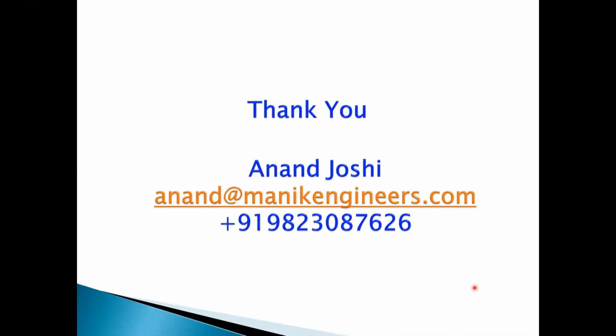To start with, you have a question from Mr. Lakshman Subramanian. Power consumption between ammonia and Freon systems has not been compared at a common condensing temperature. The ammonia system is water cooled while the Freon system is air cooled. Yes, it is done like that because that is what we observed. In cold storage applications, Freon systems are installed with air-cooled condensers, introduced as fit-and-forget units, so that is what is actually installed. We did site studies and compared them with the actual ammonia systems, which are always water cooled. So we compared those actual systems.